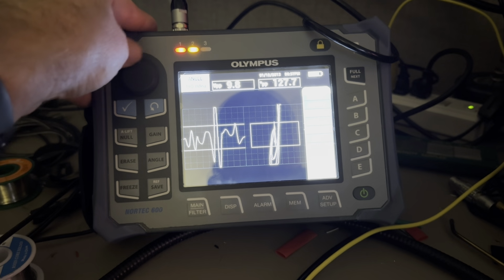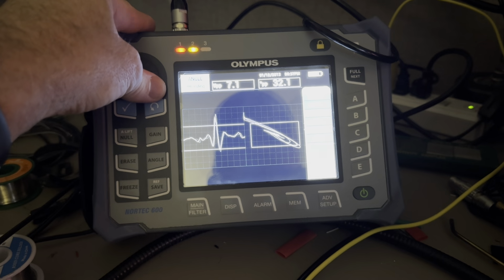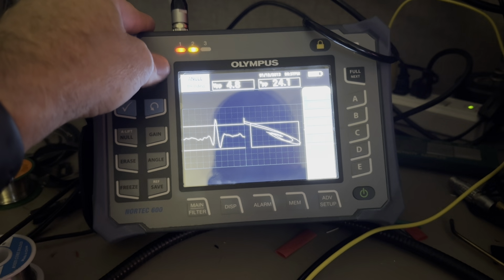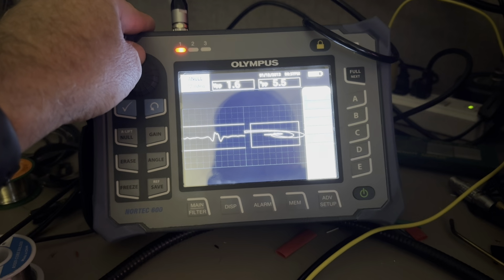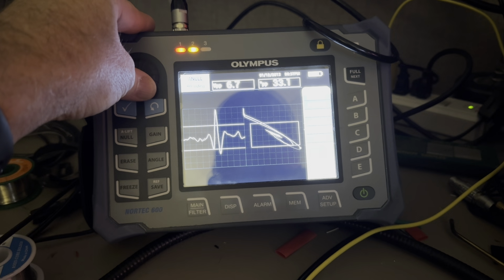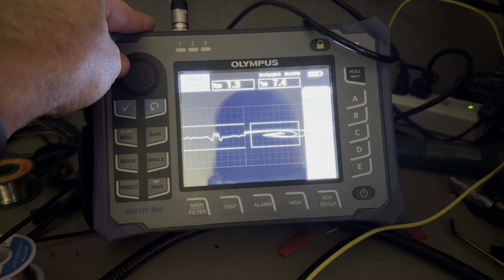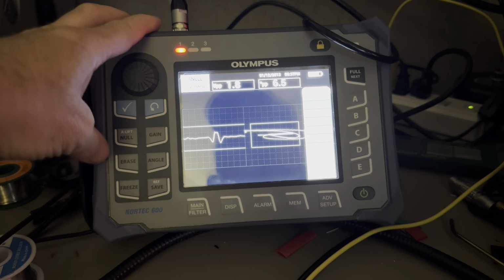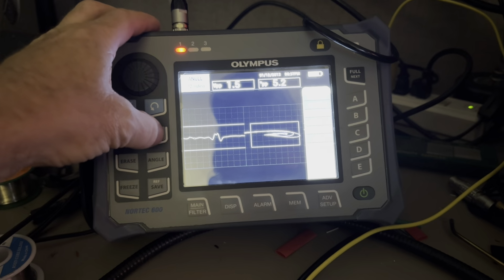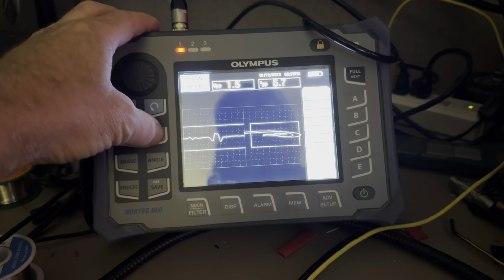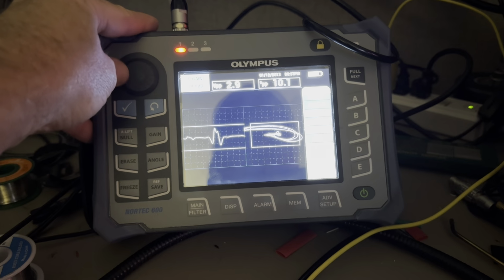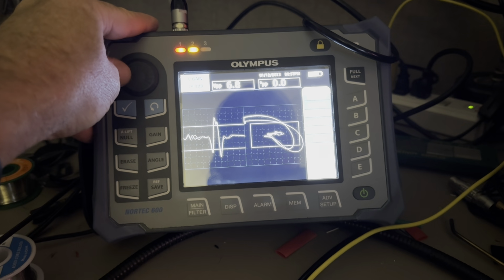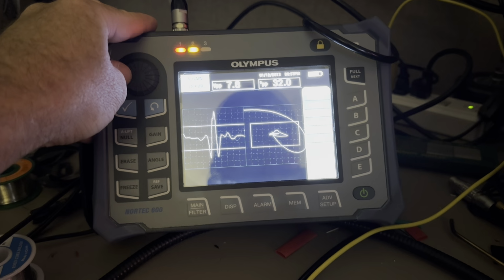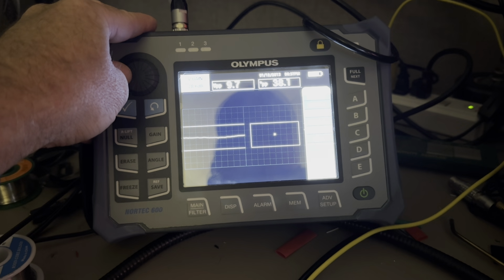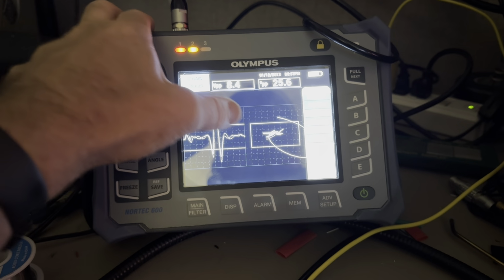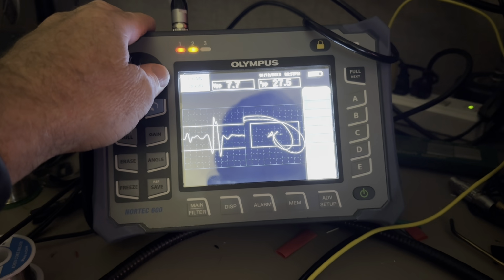Again, there's no exact phase to put that at, but you want to find a nice blend between noise and your flaw. Now what we might try here is just to crank in some more vertical gain. So there's our gain. We're gonna hit the button twice or 3 times to go to vertical gain. And we're just gonna start cranking that vertical gain up. Whoa, look at that. You're not gonna miss that, are you? Sweep display prominent. You get a huge signal there on your Lissajous.